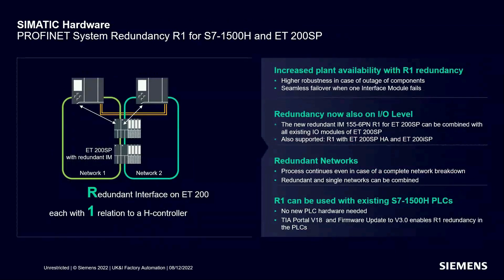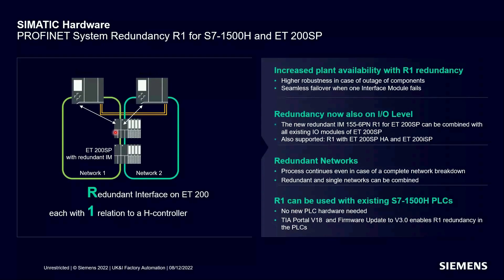Another exciting improvement is R1 redundancy for the S7-1500H. If you already have a 1500H, you can simply upgrade the firmware to version 3 to take advantage of the new features — no hardware changes required. This new capability uses a dual interface module arrangement, with one interface module reporting to the first CPU and the second to the second CPU, along the lines of traditional MRP-style networks.